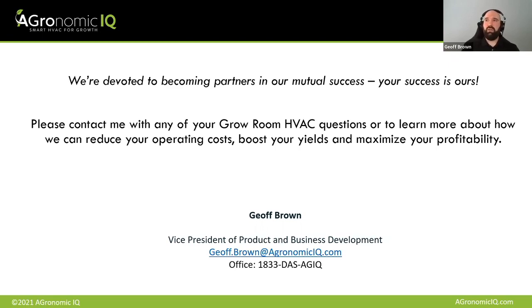That's all done internally to the unit. And so that's not an algorithm that is controlled by the user or that needs to be programmed by a local controls integrator. That's, I think, probably the biggest benefit of unitary equipment, that stuff is all baked in. We've got thousands of units out in the field with our control algorithm that does this stuff for you, basically.